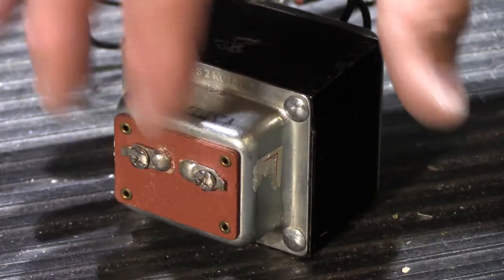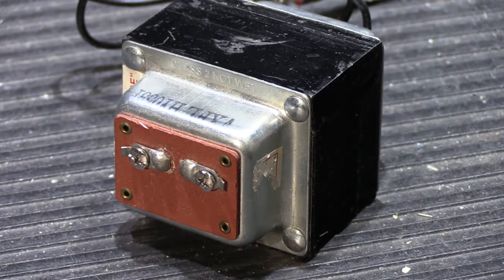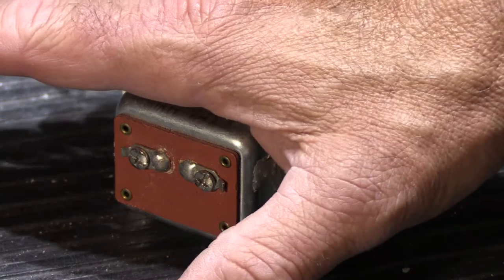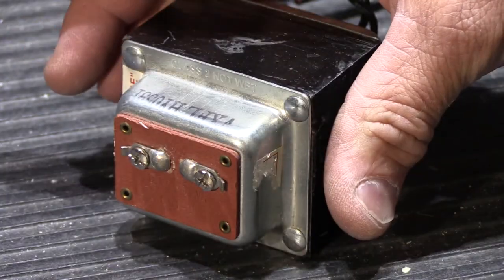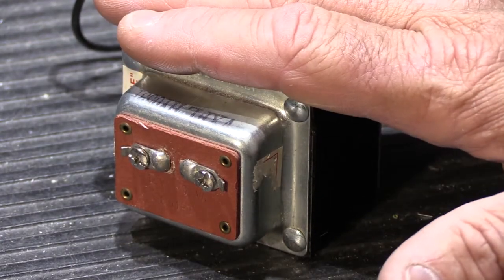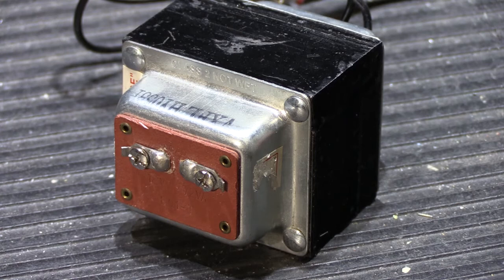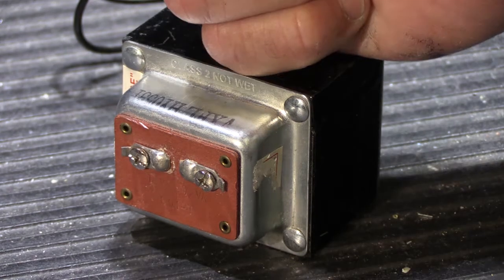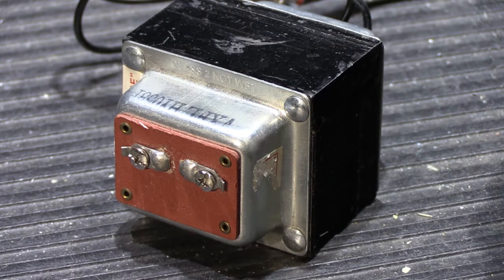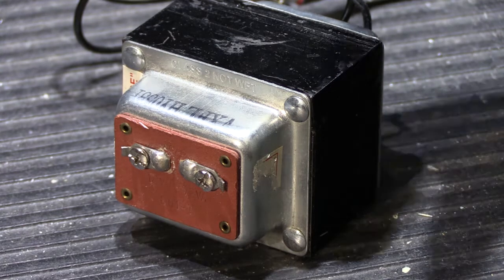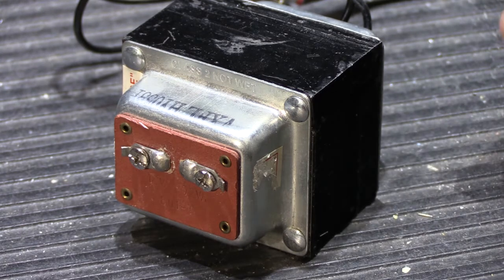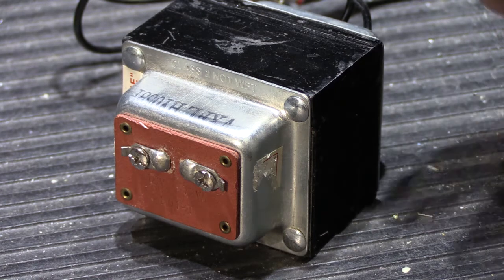Even though this transformer has the correct output on the low voltage side, nobody wants a buzzing transformer. You can't put it in somebody's house because it'll drive them crazy. Part of the reason is these transformers mount onto a metal bracket, then slide down inside the metal can, which is mounted inside the wall housing next to the back of the drywall. So a buzzing transformer on a metal bracket in a metal can amplifies the buzzing, and putting it inside a wall cavity near the drywall makes it act like a drum, becoming even louder.